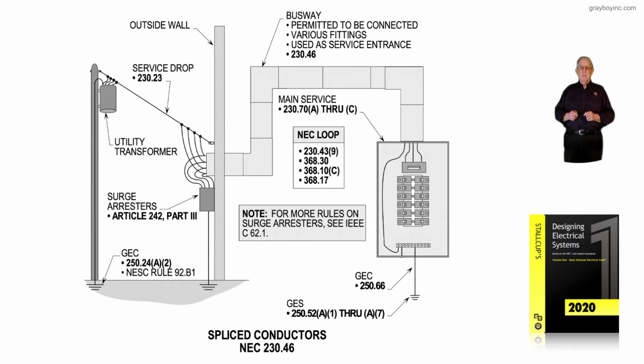Now notice we're still talking about spliced conductors, still in accordance with NEC 230.46. This particular illustration used to give us a lot of trouble. In previous times, before this permissive rule of splicing was added, the chief inspector or someone had to okay a busway, because some plan checkers, engineers, and contractors would say, hey, you're splicing those buses together. There is not anywhere in 230.46 that such permissive permission is given.